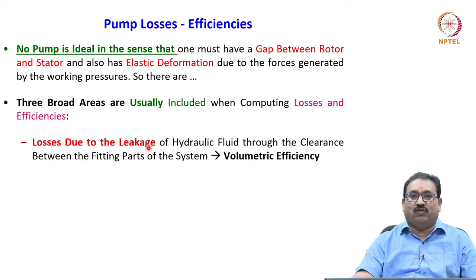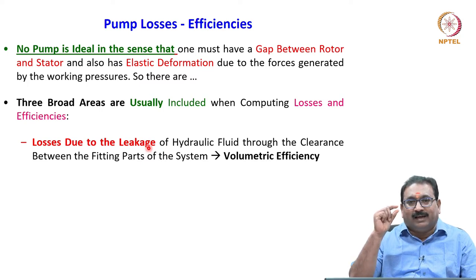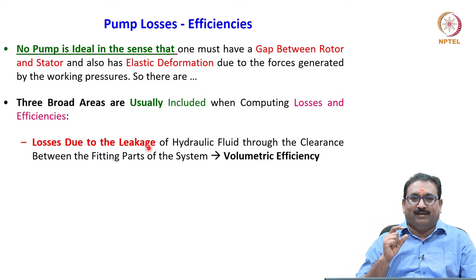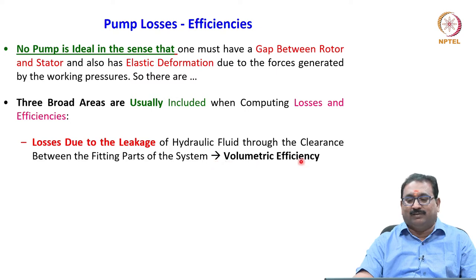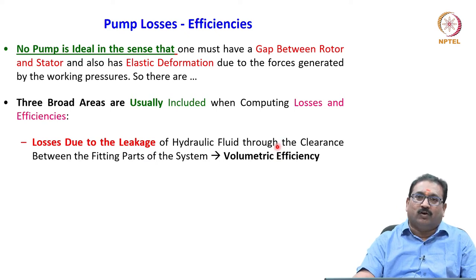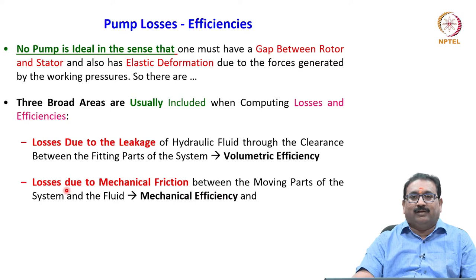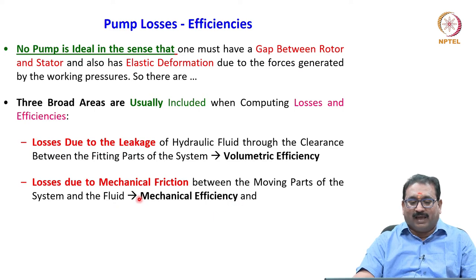The first area is losses due to leakage. Leakage occurs due to the clearance between the rotating element and the stationary element — losses due to leakage of hydraulic fluid through the clearance between the fitting parts of the system. That is what you can call volumetric efficiency. Volumetric efficiency is closely related to theoretical flow and actual flow — actual flow differs from theoretical flow. The second area is losses due to mechanical friction between the moving parts and the fluid — that is where mechanical efficiency comes into picture.